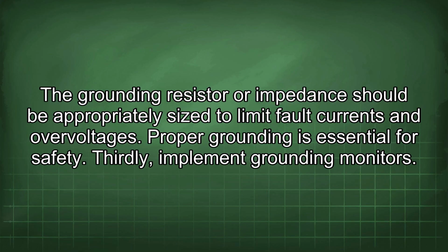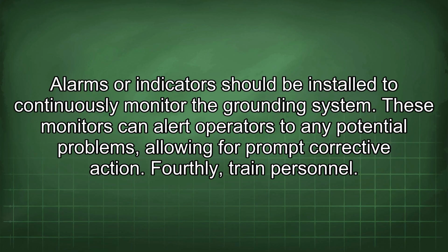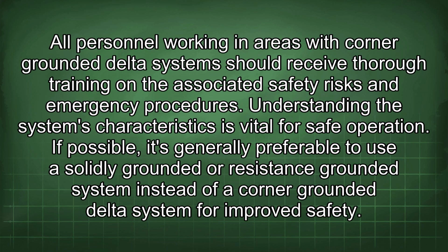Thirdly, implement grounding monitors. Alarms or indicators should be installed to continuously monitor the grounding system. These monitors can alert operators to any potential problems, allowing for prompt corrective action. Fourthly, train personnel. All personnel working in areas with corner-grounded delta systems should receive thorough training on the associated safety risks and emergency procedures. Understanding the system's characteristics is vital for safe operation.